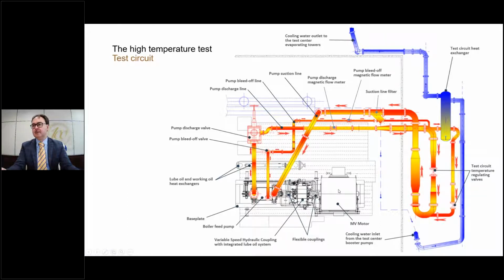2 circuits are depicted, the blue one and the red one. The blue one is the heat exchanger circuit, an open circuit where the vertical pump takes water from the pits and sends ambient temperature water to the heat exchanger. After the heat exchanger, the water is sent to the test center evaporating towers. The red circuit is the main circuit for the boiler feed water pump. Starting from the heat exchanger, the cooled water goes into the main circuit and into the suction pipe towards the suction flange, passing through the suction filter.